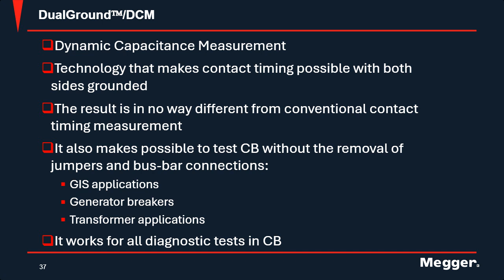Also generator breakers. If you've ever tested a generator breaker, they're usually hard bussed in there and it's very tight conditions. Everything has to be torqued. So the testing could take you a day, but the disconnecting and reconnecting can take you 2 days. And then obviously it works with all diagnostic tests for circuit breakers.